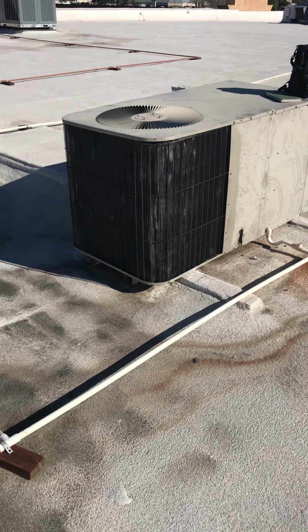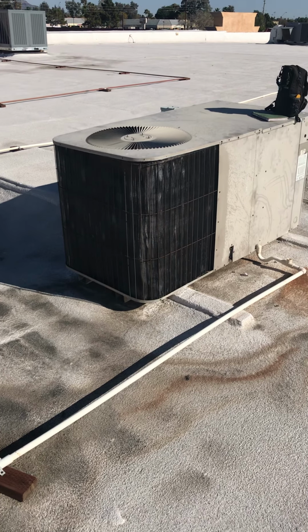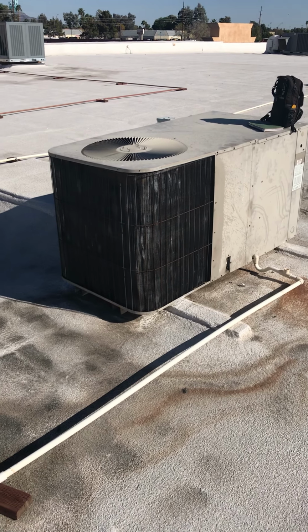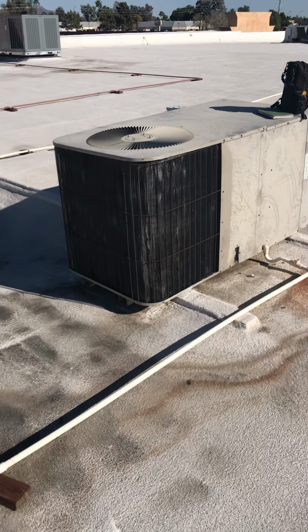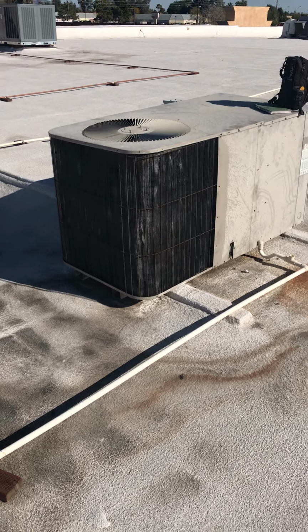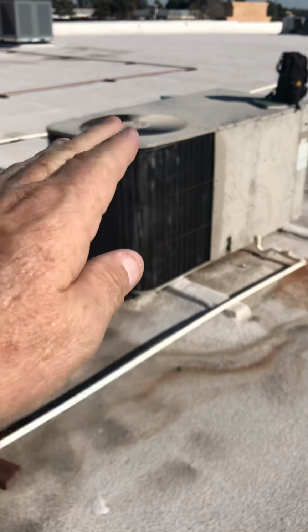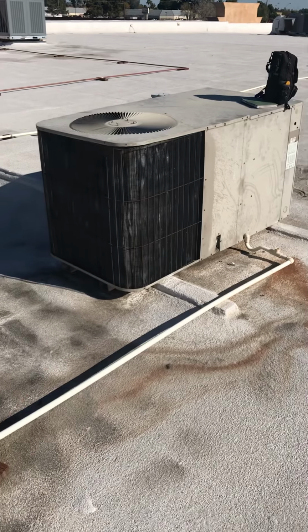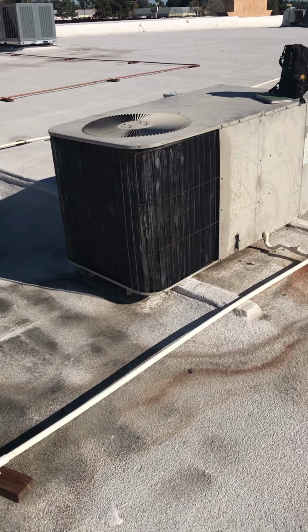A Goodman unit from around 1990 to 1995, maybe late 90s. We're looking at a unit replacement. She's been running great since the 90s, but there's some damage in here - there's an evaporator coil leak, and the customer doesn't want to replace the coil.